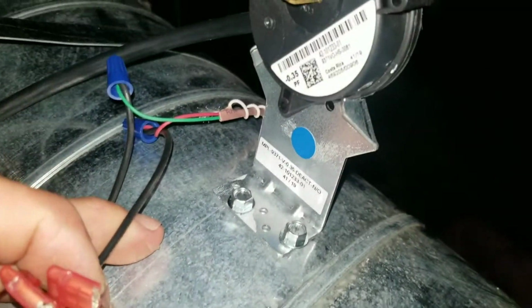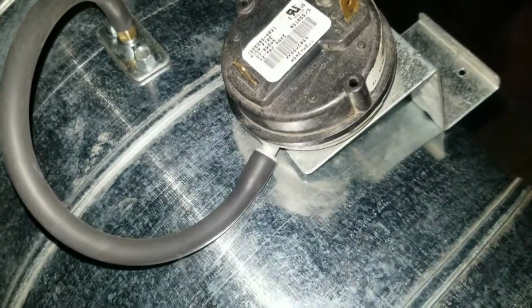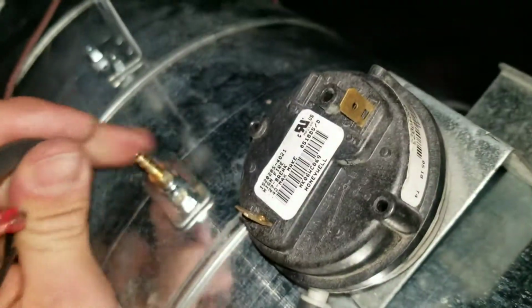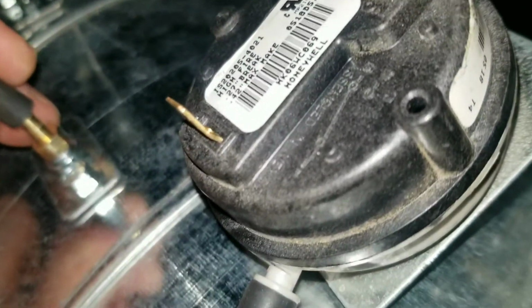So I'm right at that 0.35 rating, and it doesn't seem to want to close. So got another one here. This is just a used spare on my truck. And it's actually closing. So for testing purposes, we're going to leave this here, and then we'll have to get us another new pressure switch at a lower rating.